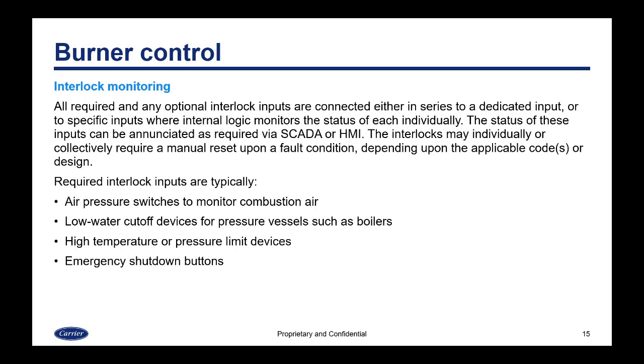All required and optional interlock inputs are connected either in series to a dedicated input or to specific inputs where internal logic monitors the status of each individually. The status of these inputs can be annunciated via SCADA or HMI. The interlocks may individually or collectively require a manual reset upon a fault condition. Some required interlocks you might typically see are air pressure switches to monitor combustion air, low water cutoff devices for pressure vessels such as boilers, high temperature or pressure limit devices, and emergency shutdown buttons.